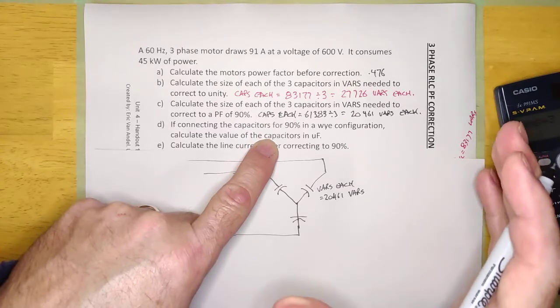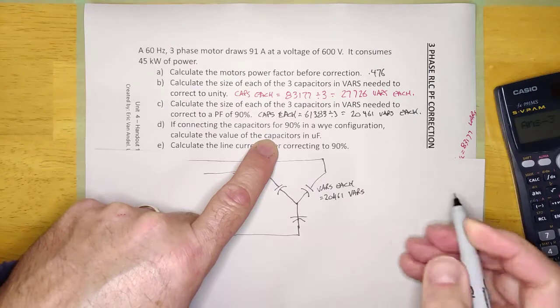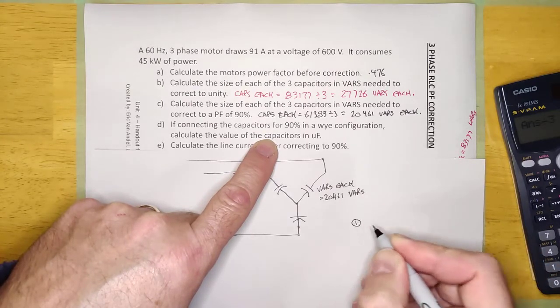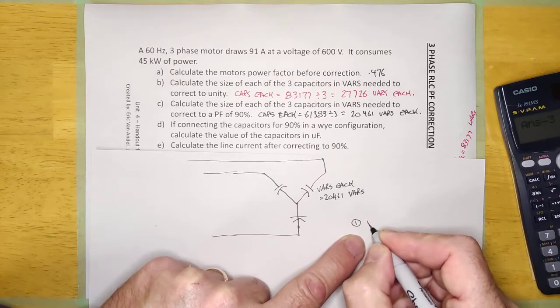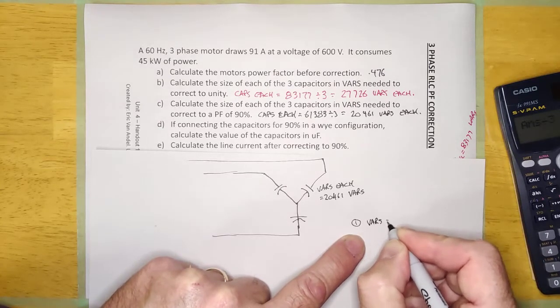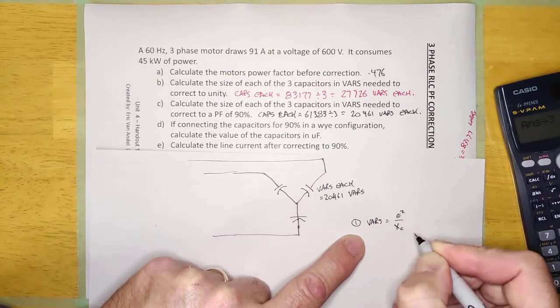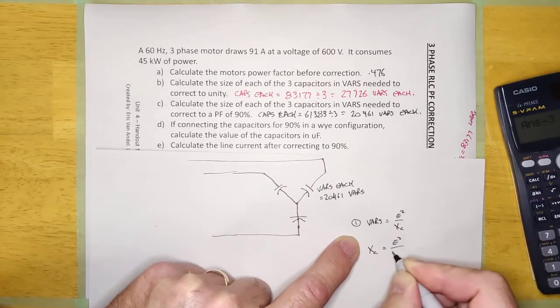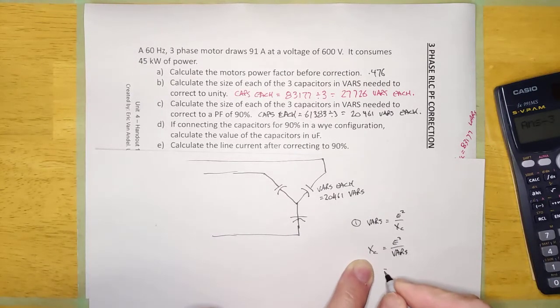This is going to be very similar to single phase. If you know the VARs of the capacitor, it's going to be a two-step process. And so, step one was use this formula right here to calculate how many ohms it is. VARs is equal to E squared over XC. And so, XC is equal to E squared over VARs. And we're going to figure out how many ohms this thing is.